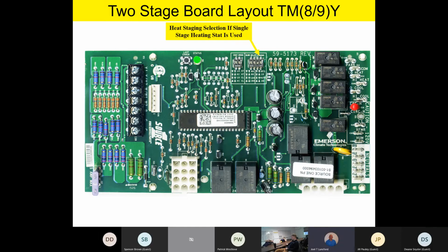Okay, right next to it, this is one set of adjustments that I really like about this board. This is our heating staging if a single stage thermostat is used. Let me say this one more time. Let's say you're stuck with a single stage thermostat. You don't have enough wires behind the wall, or maybe the homeowner just loves that old Honeywell round Mercury thermostat. And yes, it would work fine with an old Mercury single stage thermostat. So if you're stuck with a single stage thermostat for whatever reason, we can give you some staging by manipulating these dip switches.